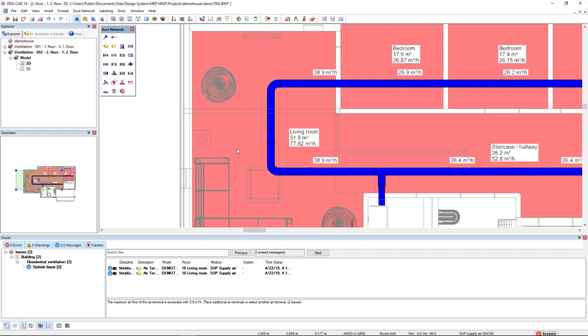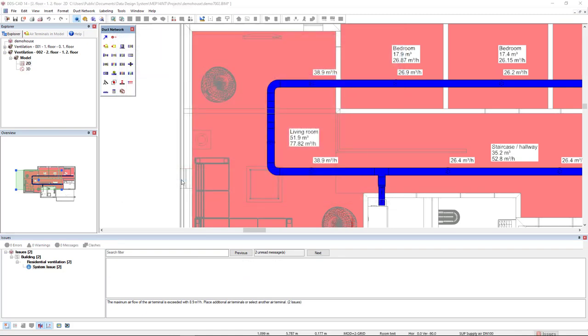Now, if we recalculate, come to the air terminals. Split airflow. And now we see that we have three air terminals in the living room. And all the values are within the 330 cubic meters per hour.